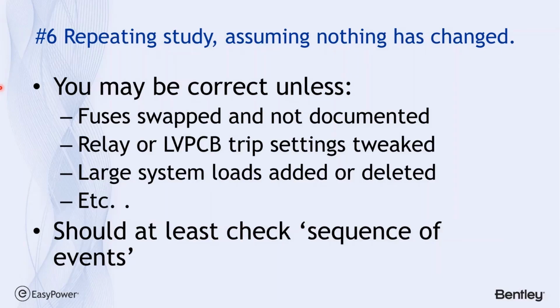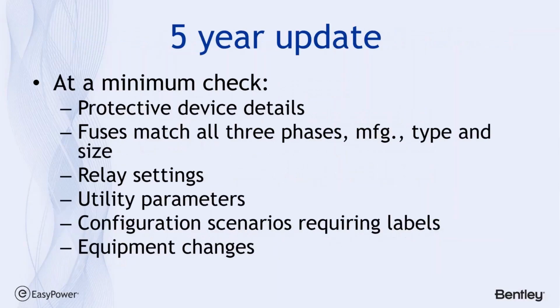Again, it seems kind of common sense, but it frequently comes up that for whatever reason, the client may not have wanted to pay for it. So at the minimum, you want to have protective device details verified. Make sure all fuses match in all 3 phases. And again, taking a picture is a good way to verify that. Verify relay settings, utility. Now, utility companies can have changes in their data, and they're not obligated to tell you about it. So checking with the utility on all updates is mandatory. And then you want to make sure you have scenario configurations for doing labels and comparing that against what your label conditions were from the last study.